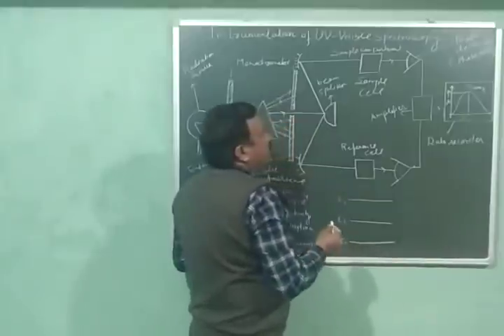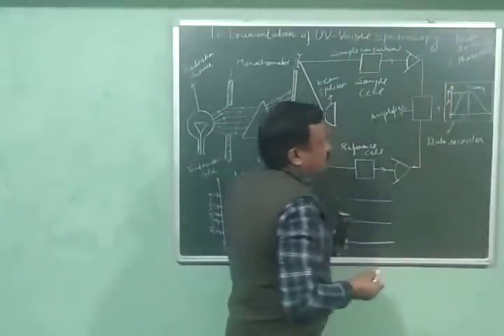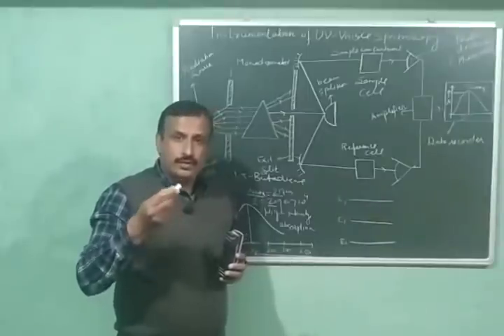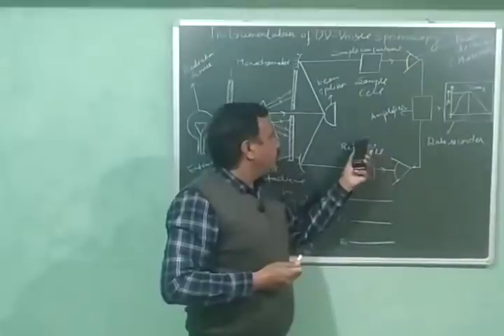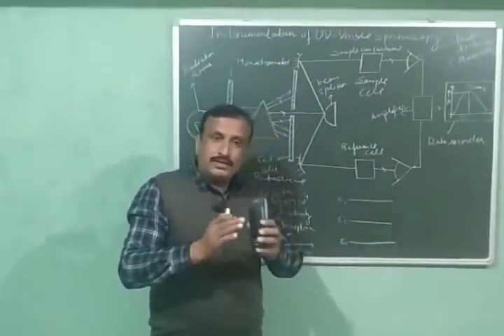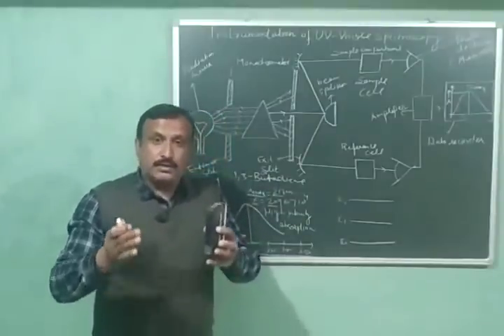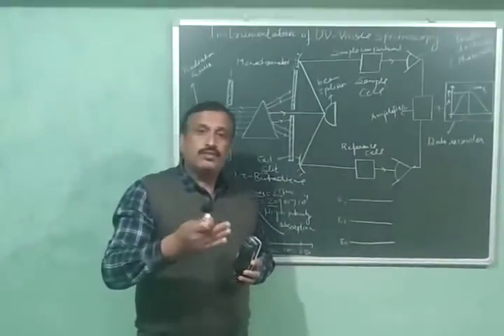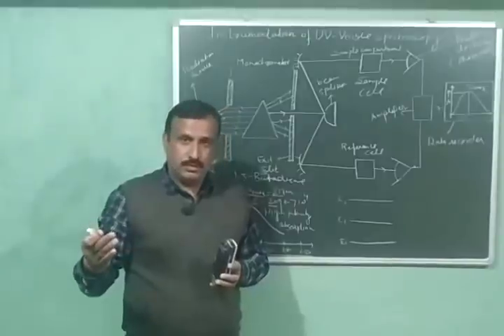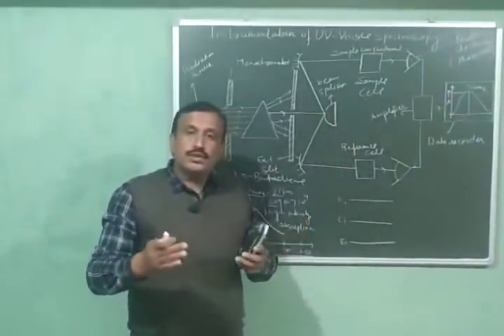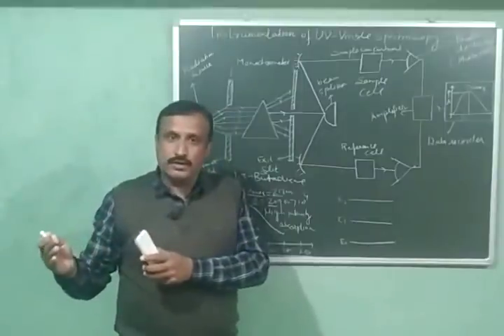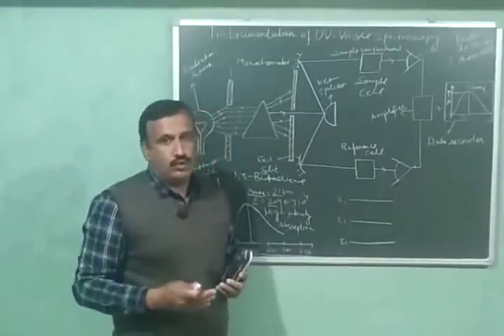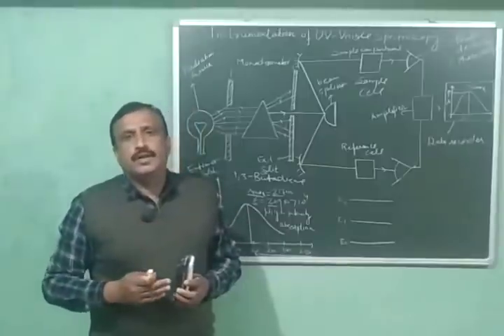The intensities of transmitted light from the sample cell and the reference cell are measured with the help of photo detectors having photo cells. The photo detector also calculates the ratio of intensities of the beams transmitted from the sample cell and the reference cell. The instrument automatically subtracts the absorbance due to the solvent from the absorbance of the solution, so we are left with the absorbance only due to the sample.